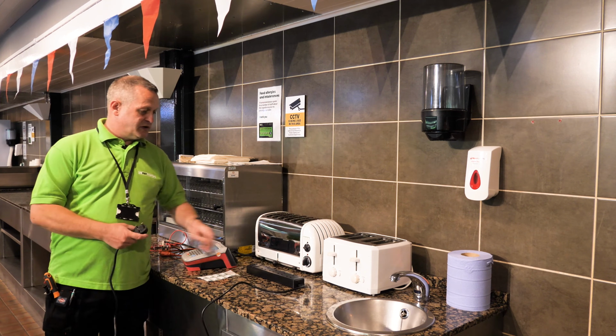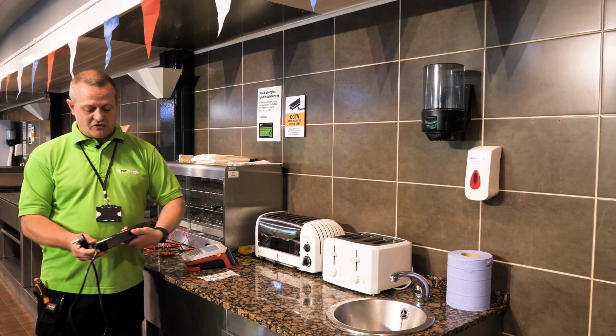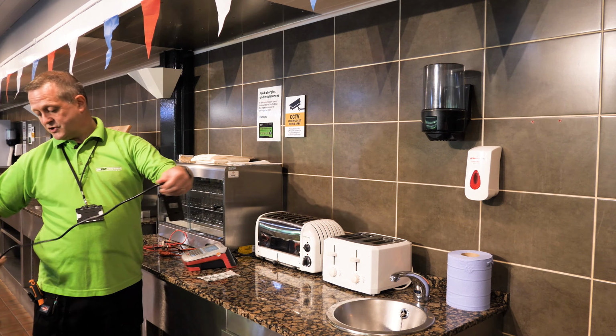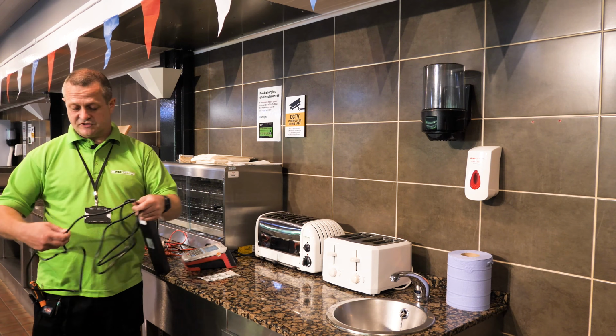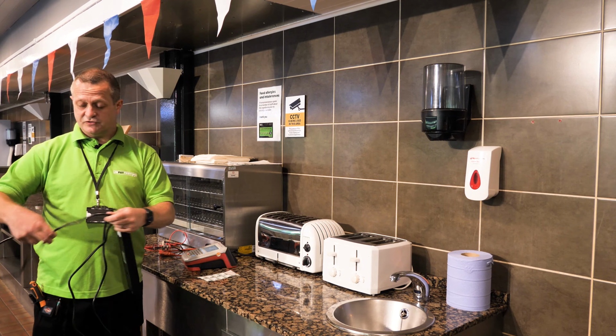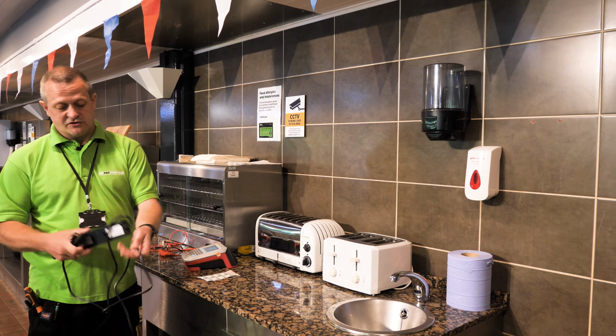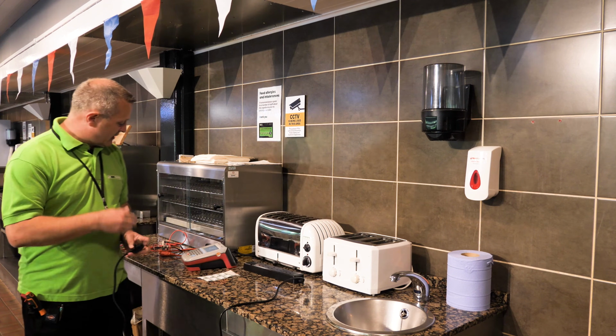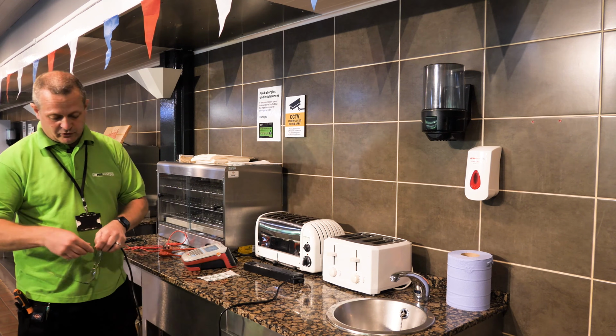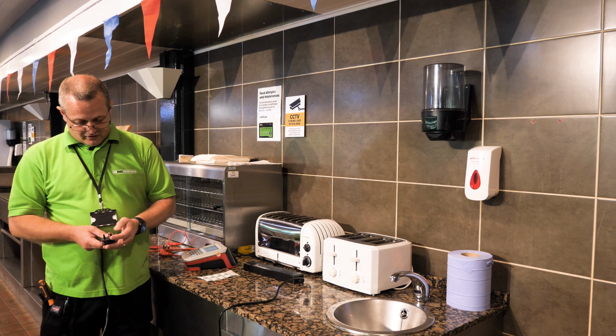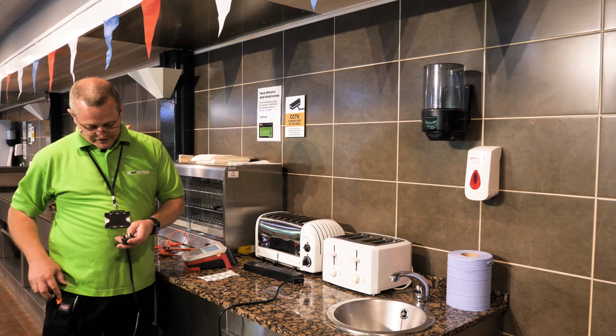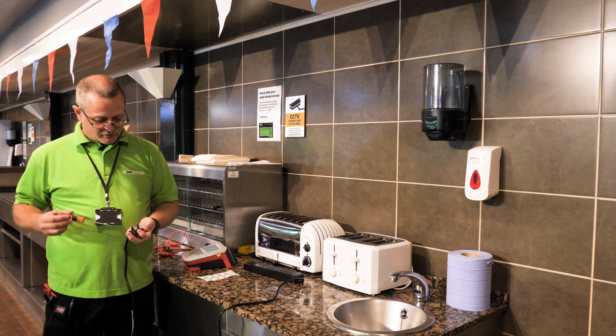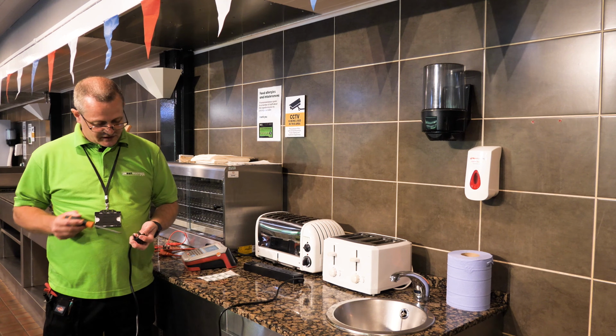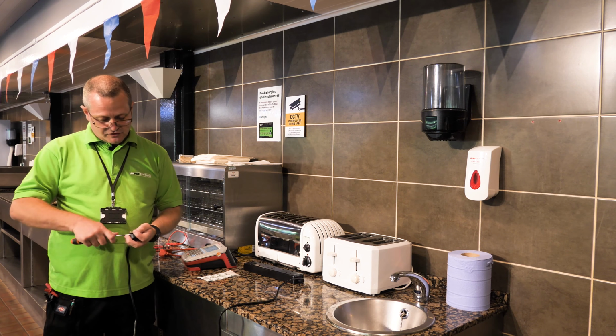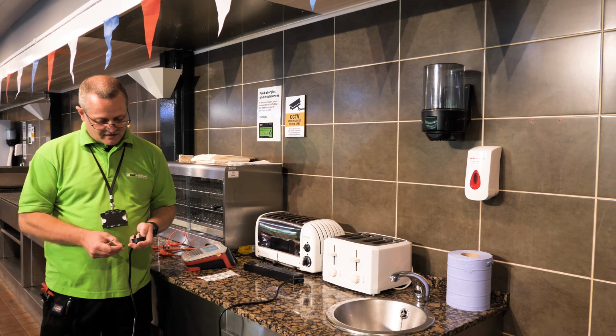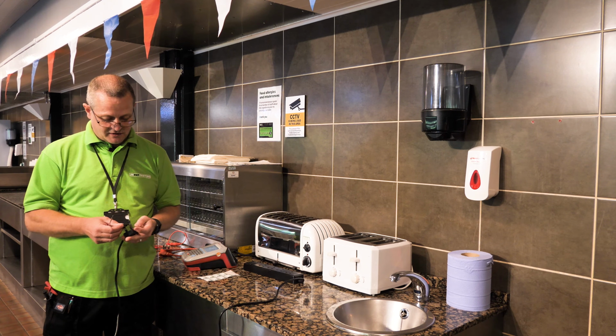So what we're going to do first of all is do a visual inspection, make sure that there's nothing giving us anything concern, quick check along the cable, make sure there's no cuts, tears in the sheath, certainly no exposed metal cabling coming through, so I'm happy with that. So then I'm going to check the plug. This is a moulded plug, so a quick look on the plug, and I can see that it's got a 13 amp fuse recommendation for the extension lead. So we'll just expose the fuse just to make sure that it is actually in fact a 13 amp fuse inside it, and it is.